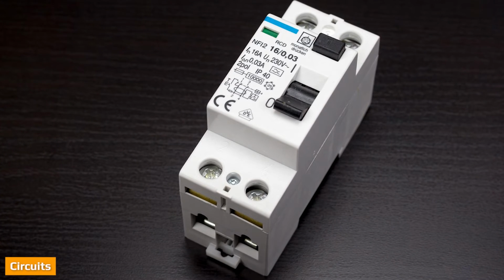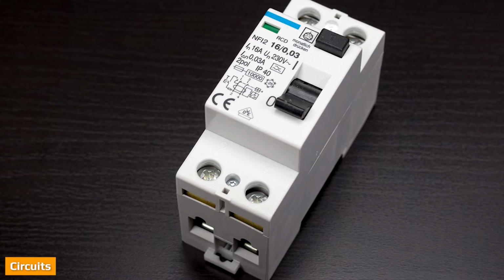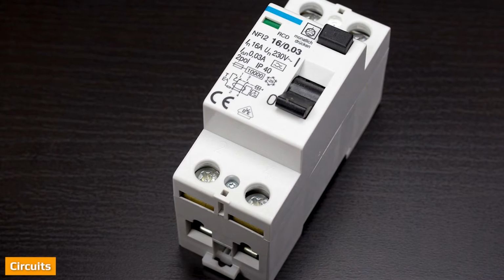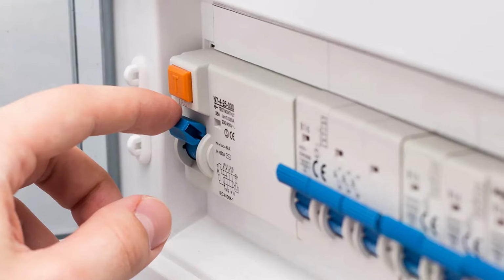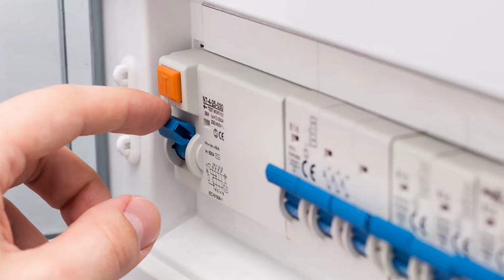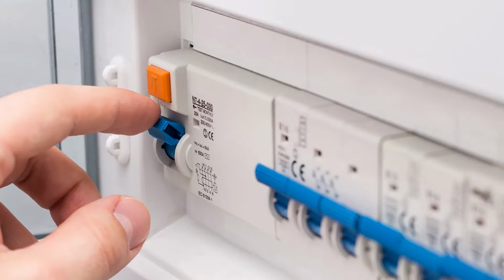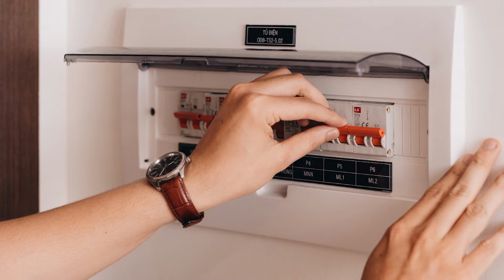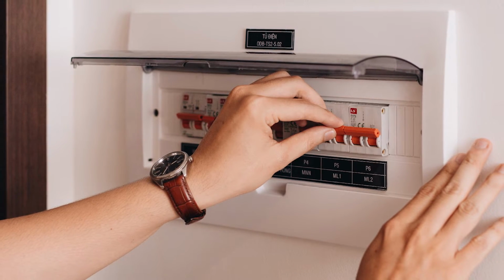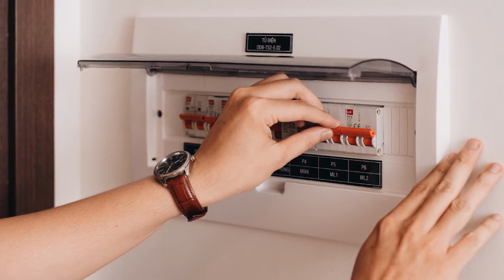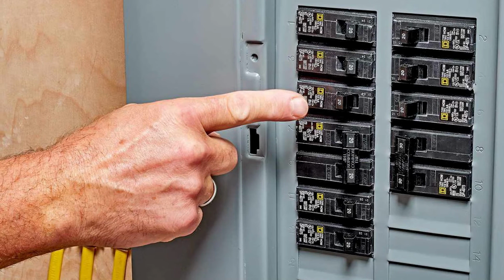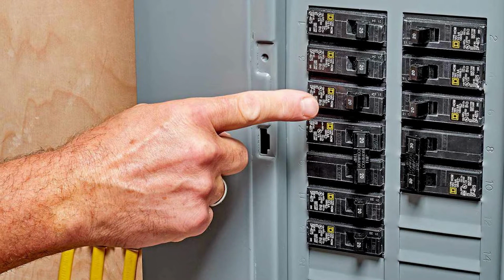Outlets, receptacles, switches, light fixtures, and other electrical devices typically are wired in multiples on a single circuit. With the first device, the line is the wire running from the service panel to the device, and the load is the wire running from the first device to the second device downstream on the circuit. At the second device, the line is the power source coming in from the first device, the load is the wire going out to the third device on the circuit, and so on.